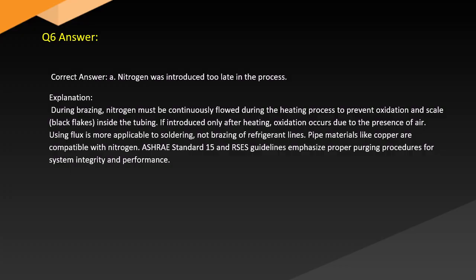Answer. Correct answer: A. Nitrogen was introduced too late in the process. Explanation. During brazing, nitrogen must be continuously flowed during the heating process to prevent oxidation and scale, black flakes inside the tubing. If introduced only after heating, oxidation occurs due to the presence of air. Using flux is more applicable to soldering, not brazing of refrigerant lines. Pipe materials like copper are compatible with nitrogen. ASHRAE Standard 15 and RSES guidelines emphasize proper purging procedures for system integrity and performance.